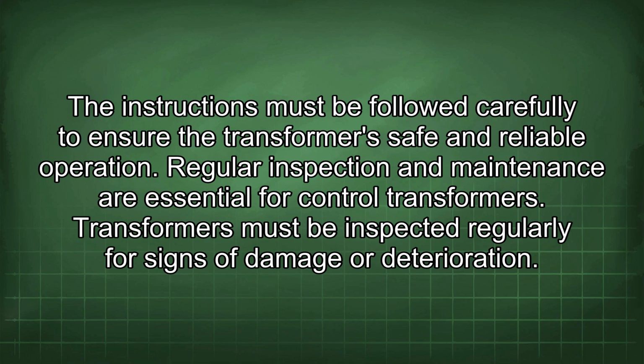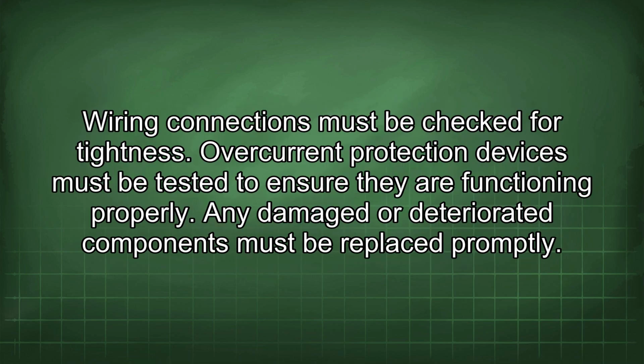Regular inspection and maintenance are essential for control transformers. Transformers must be inspected regularly for signs of damage or deterioration. Wiring connections must be checked for tightness. Overcurrent protection devices must be tested to ensure they are functioning properly. Any damaged or deteriorated components must be replaced promptly.